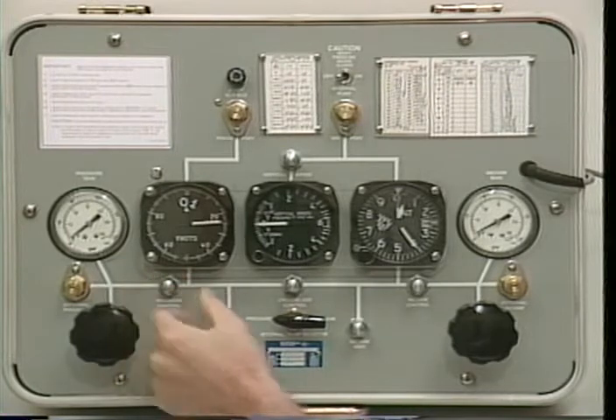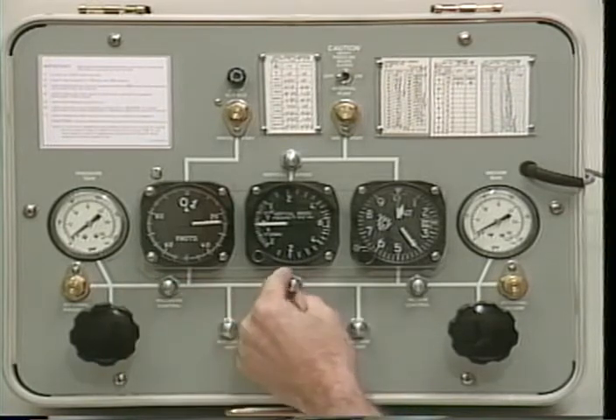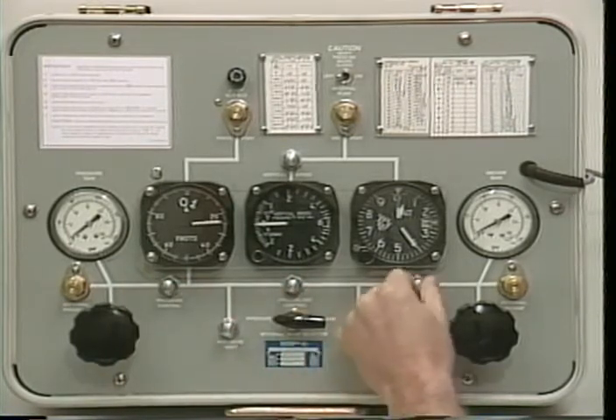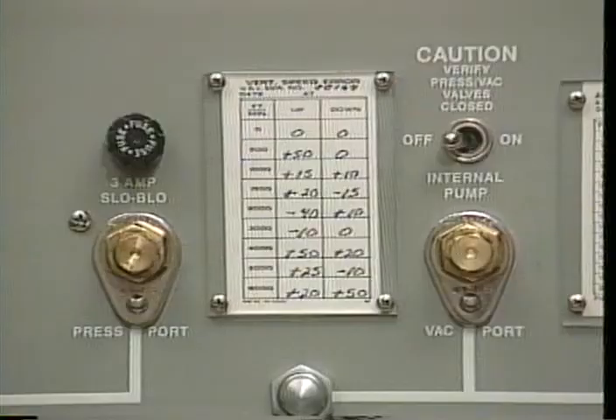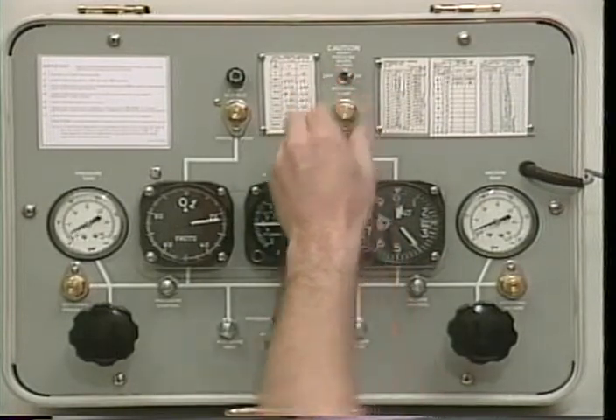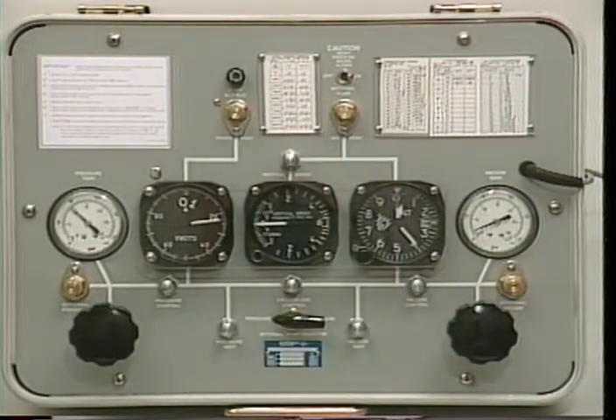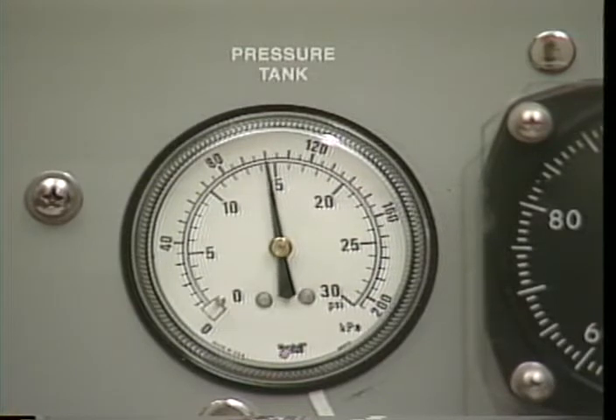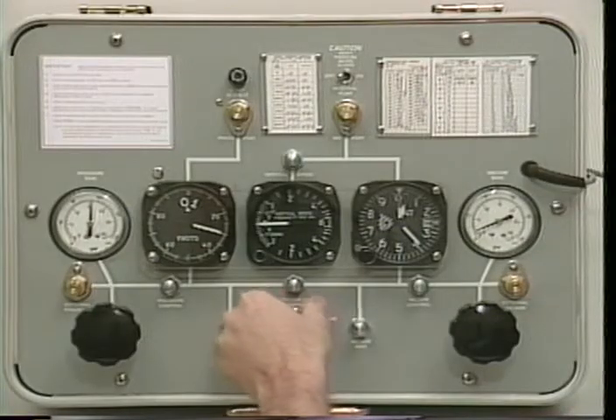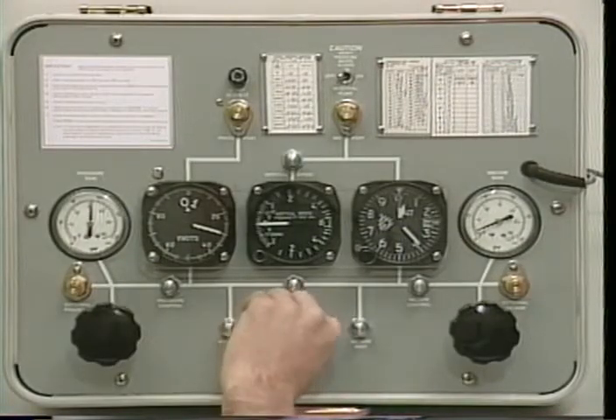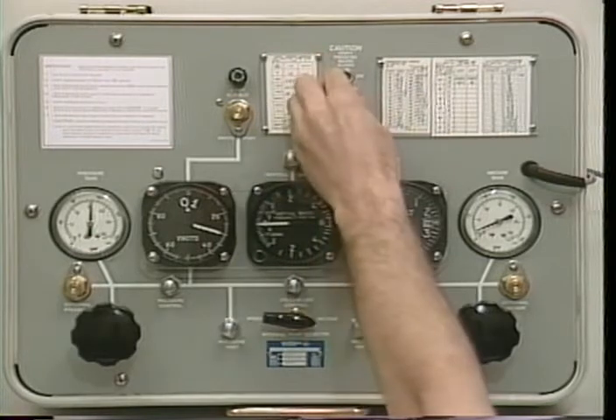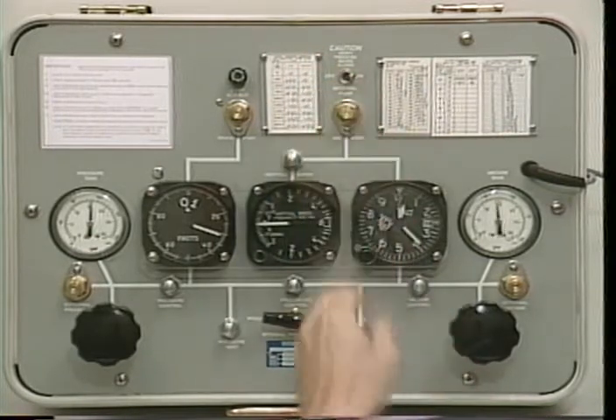The first step is to make sure all valves are fully closed by turning them clockwise. Then, cap and seal both outlet ports. Turn on the internal pump switch, or use hand pumps, and pump the pressure tank reservoir to at least 15 psi, as indicated by the pressure tank gauge. Turn on the internal pump, or use hand pumps, to increase the vacuum in the vacuum tank to 25 inches.